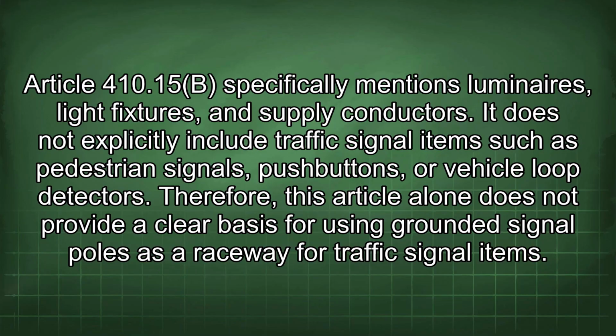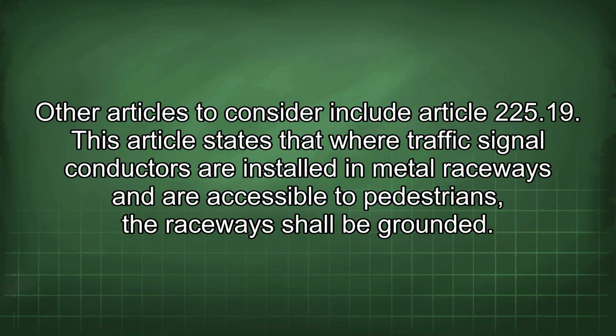Article 410.15b specifically mentions luminaires, light fixtures, and supply conductors. It does not explicitly include traffic signal items such as pedestrian signals, push buttons, or vehicle loop detectors. Therefore, this article alone does not provide a clear basis for using grounded signal poles as a raceway for traffic signal items.